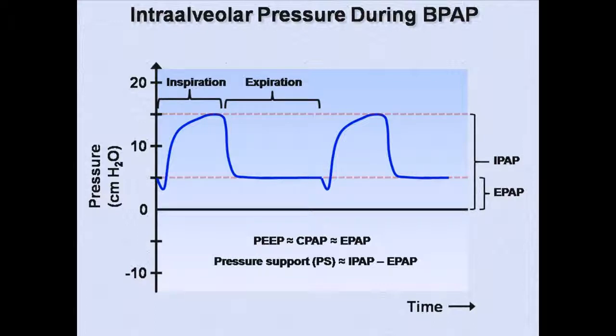Unlike with CPAP, some machines that deliver BPAP can also provide what's known as a backup rate, whereby the machine itself will initiate an inspiration if a certain period of time has elapsed without a patient-triggered breath. A BPAP mode with a backup rate is sometimes referred to as ST mode for spontaneous or timed. This is to distinguish it from S mode or spontaneous only mode, where inspiration can only be triggered by the patient and not the machine.